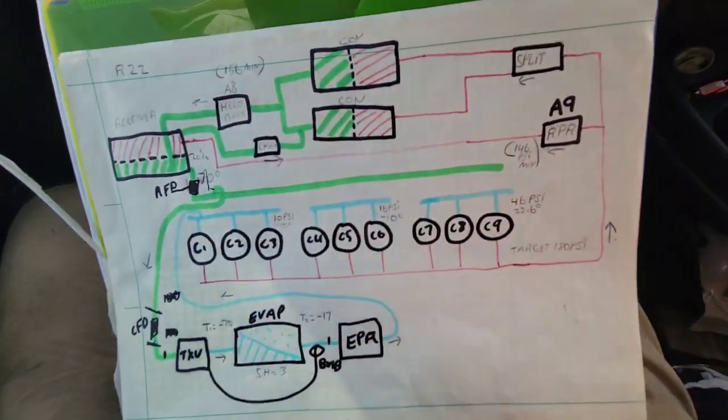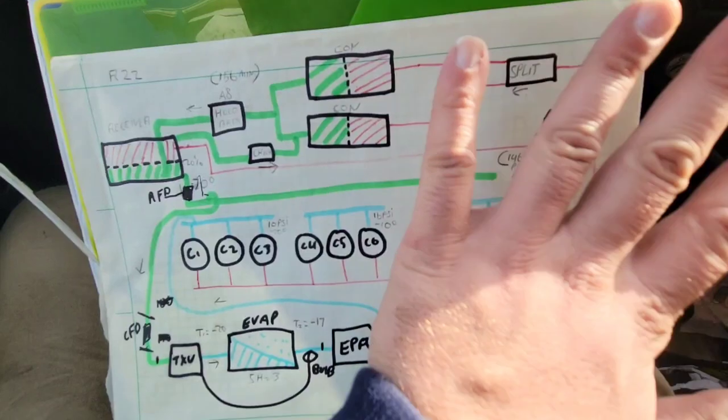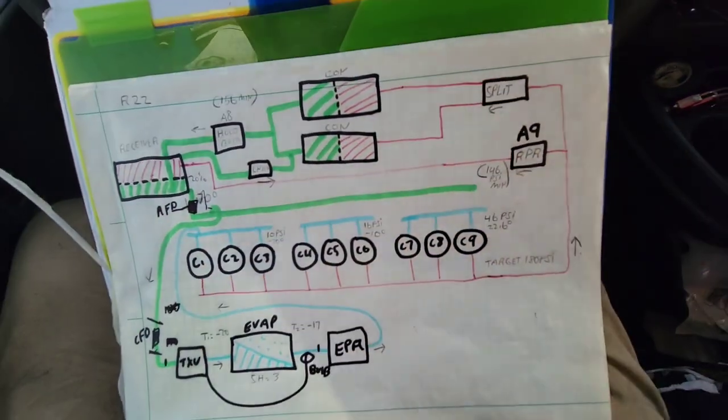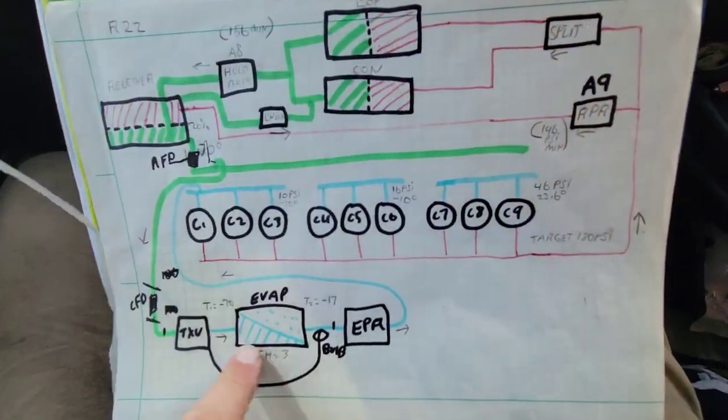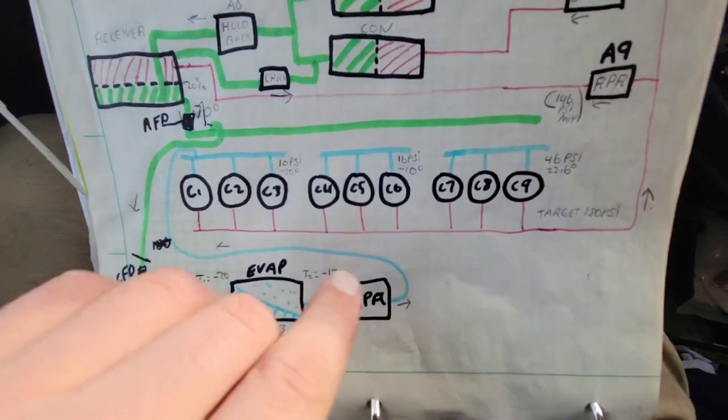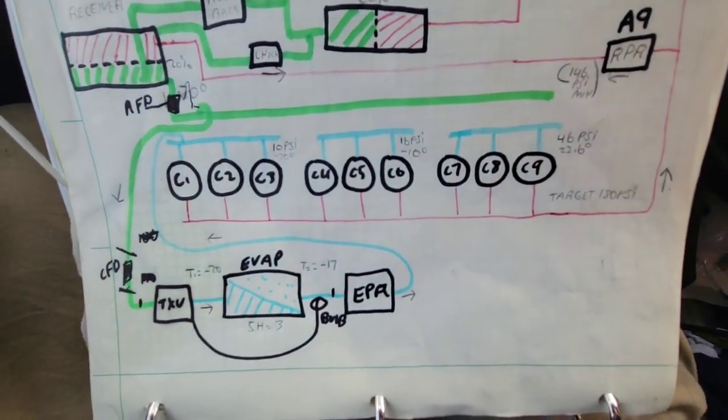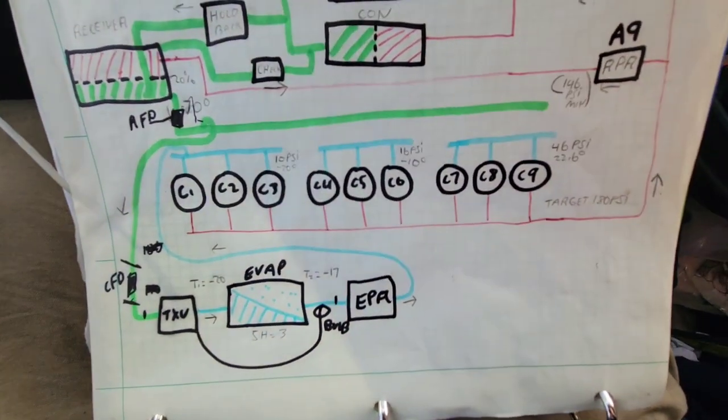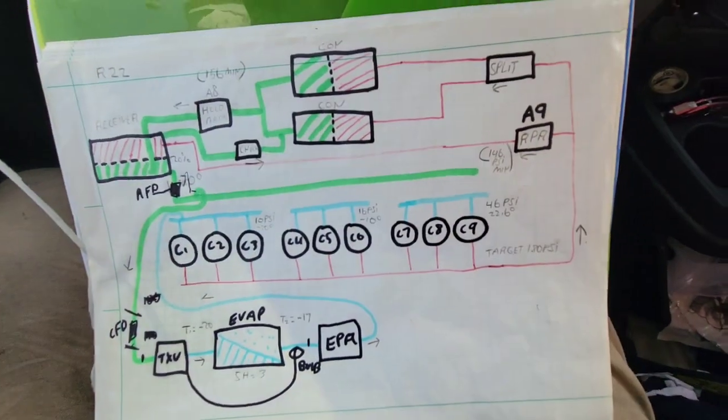Now, in the example I give, as I mentioned, I go through this whole thing, but I made an assumption that the temperature was okay. So you'll actually see me get to this TXV step, and I'm still trying to justify. I'm still convinced that it's the TXV screen. But it's not, it's the temperature probe.